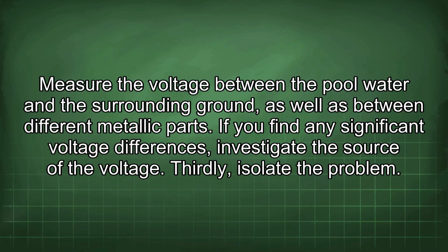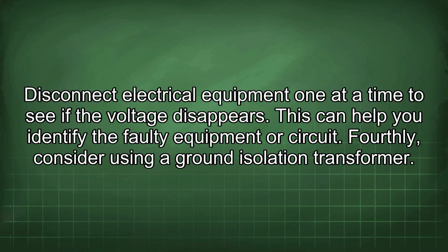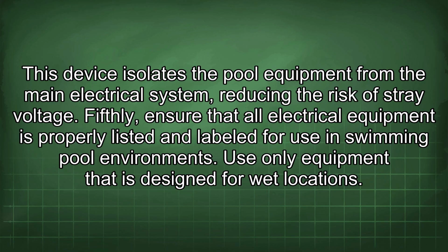Thirdly, isolate the problem. Disconnect electrical equipment one at a time to see if the voltage disappears. This can help you identify the faulty equipment or circuit. Fourthly, consider using a ground isolation transformer. This device isolates the pool equipment from the main electrical system, reducing the risk of stray voltage.